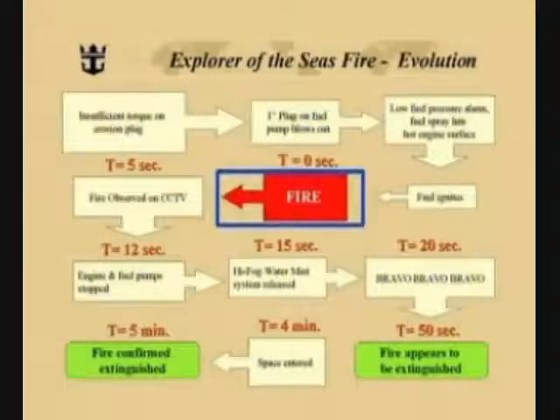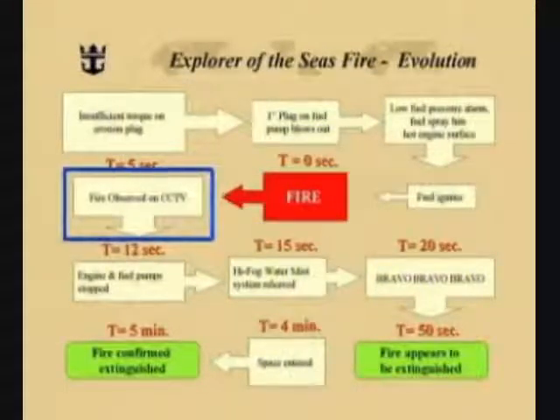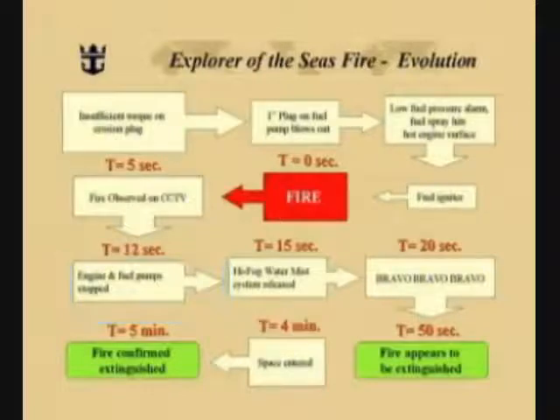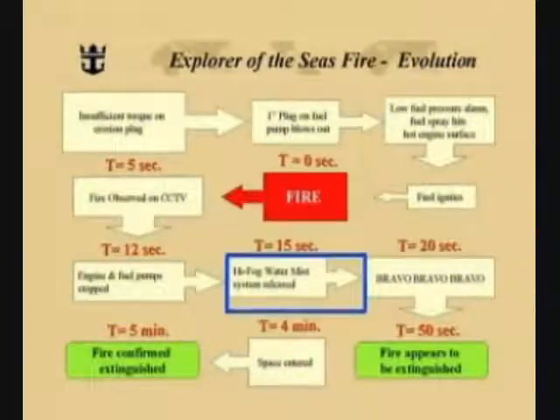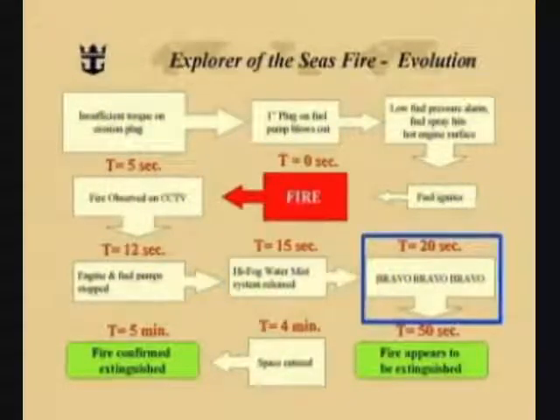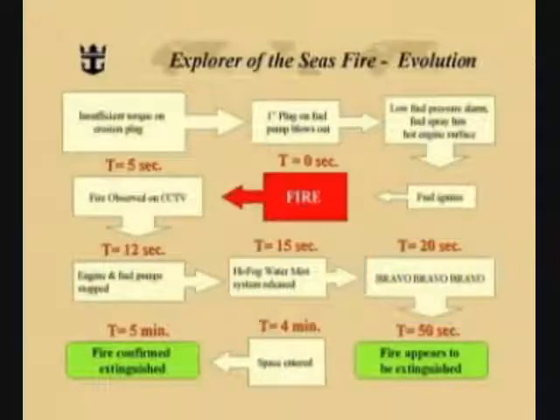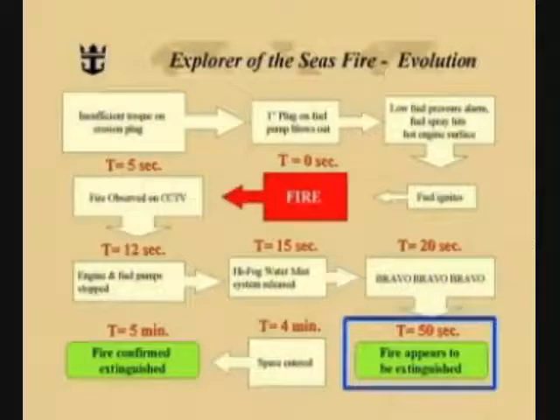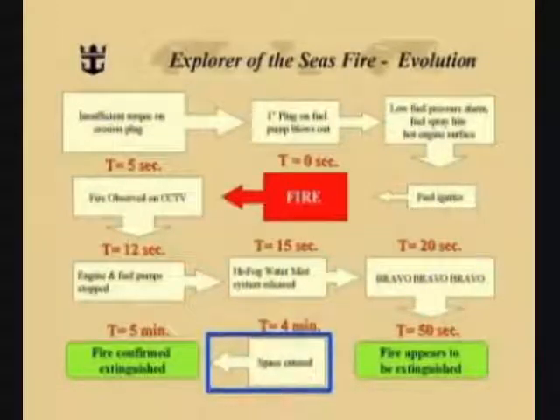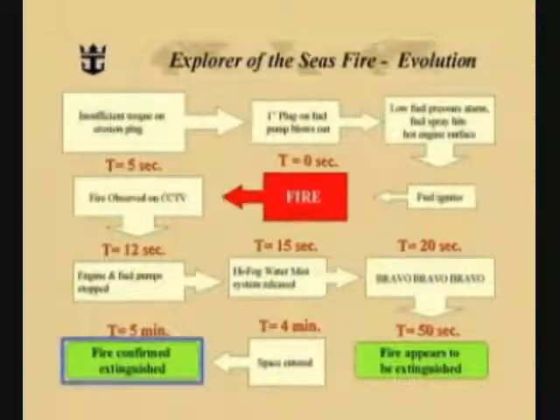Our timer starts here. Five seconds later, the fire was observed in the closed-circuit television system in the control room. Seven seconds later, the engineers stopped the engine and the fuel pumps. Three seconds after that, the Hi-Fog water mist system was released. At 20 seconds into the event, the Bravo, Bravo, Bravo signal was sounded from the bridge. Fifty seconds after the fire first ignited, it appeared to be extinguished from the closed-circuit television monitors. Four minutes after that, the space was re-entered, and five minutes after the initial fire was detected, the fire was confirmed extinguished.